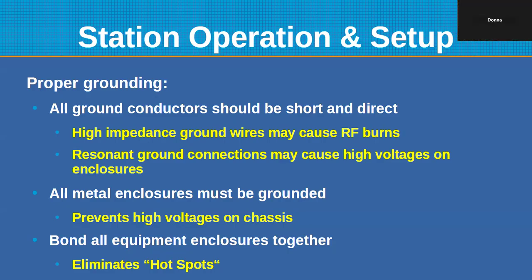Okay, all right, thanks. What do you mean by bonded? Physically connected, usually with some sort of clamping device like a bolt and nut. I think it's probably coming up on the next slide or two. You do not want to use soldered connections, particularly for any ground wire that might be carrying current as a result of a lightning strike, because you're talking about potentially thousands of amperes, and solder would vaporize, and you no longer have a connection. Whereas a physical crimped or welded connection could withstand the current.